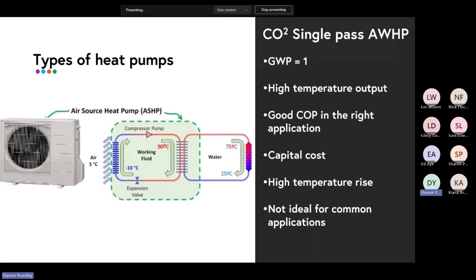So what you tend to see with a CO2 based system is they have this, what do they call it, a shift load system. So rather than have, let's say for instance, you've got 3 hot water cylinder storages, rather than have 3 in parallel, which would be most common for a gas-fired system. And the reason for that is, if let's say you've got 3 1,000 litre tanks, if you have them connected together in parallel on the potable side, it means that if you've got 3 tanks, they'll all be at 65 degrees. You'll have 3,000 litres of 65-degree water ready to deliver to the building.